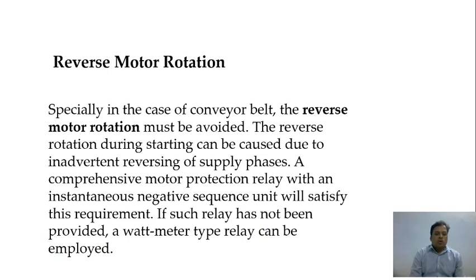Now we also come to reverse motor rotation, where the motor starts rotating in the reverse direction. How is it possible? Especially in the case of a conveyor belt, reverse motor rotation must be avoided. Why should it be avoided? Reverse rotation during starting can be caused by inadvertent reversing of supply phases. A comprehensive motor protection relay with an instantaneous negative sequence unit will satisfy this requirement.